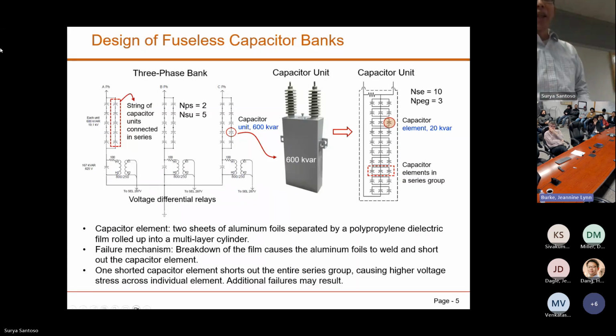So this is a 3-phase bank, and this is an individual bank. A, B, and C are all identical. Inside each individual bank you have these capacitor units, and each capacitor unit is rated 600 kVAR. By the way, the entire 3-phase bank is 18 megaVAR, but each one of these is just 600 kVAR at 19.1 kV. And in the real world, it looks like this.